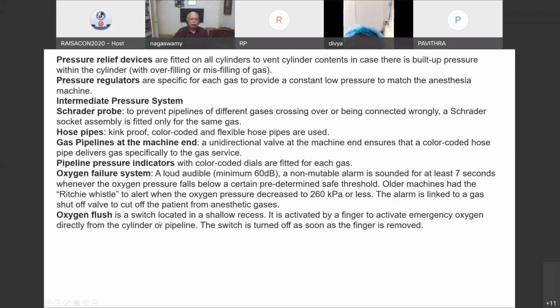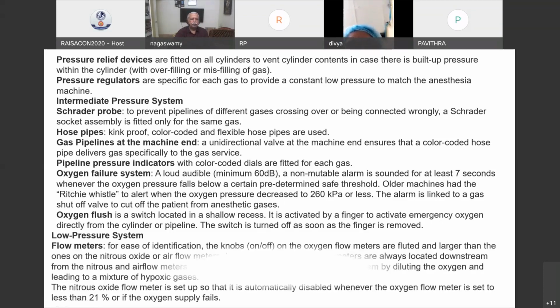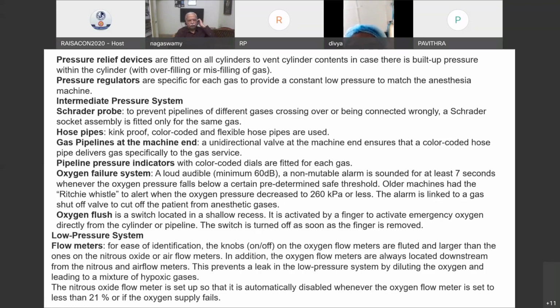And the oxygen flush is a switch located in a shallow recess. So normally it will not be on the surface, it will be inside a small depression so that it will not be accidentally turned on. That is another safety mechanism. Then coming to the low pressure system, the flow meters consist of low pressure parts. So for easy identification, the knobs are fluted and larger, color coded. The names are written on them. All these things you normally prepare for your Viva, you know all these things.